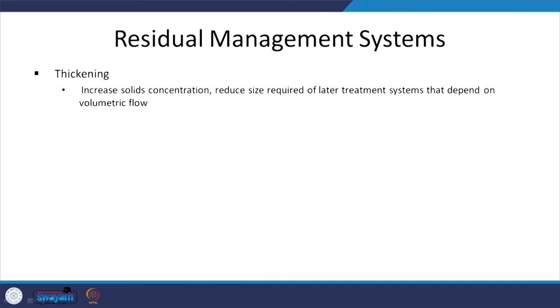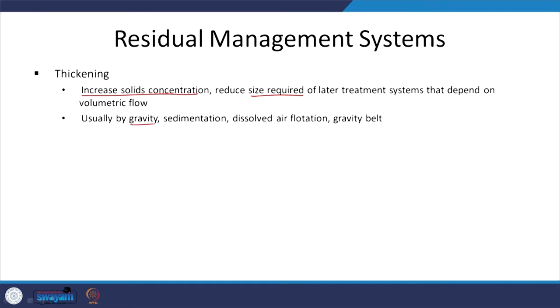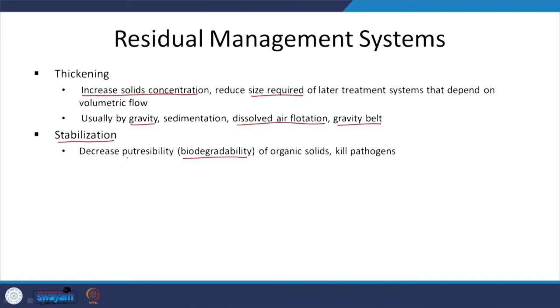The first one is thickening. What are we trying to do? Increase the solids concentration. Why? Because that will lead to reduced size requirements for the later treatment systems. We achieve that typically by gravity and, depending upon the type of sludge, by dissolved air flotation or gravity belt. Then stabilization — the secondary treatment unit sludge is biomass, it is active, so it will decay if we do not stabilize it. We are trying to decrease the biodegradability, meaning the putrescibility, of organic solids, and in the process we want to kill any pathogens in the sludge.